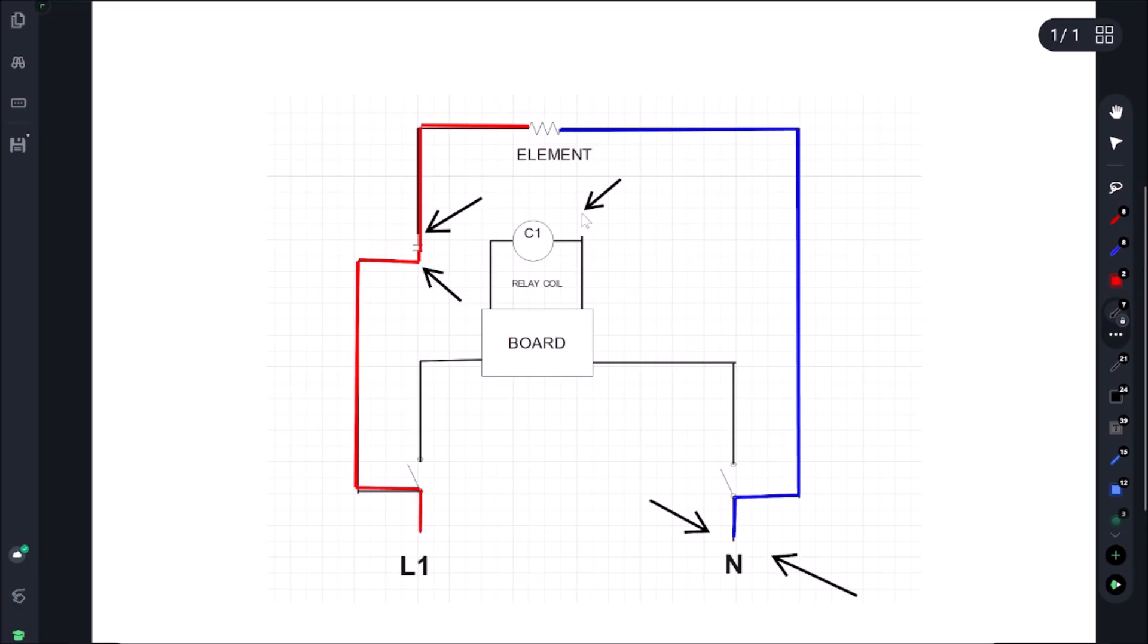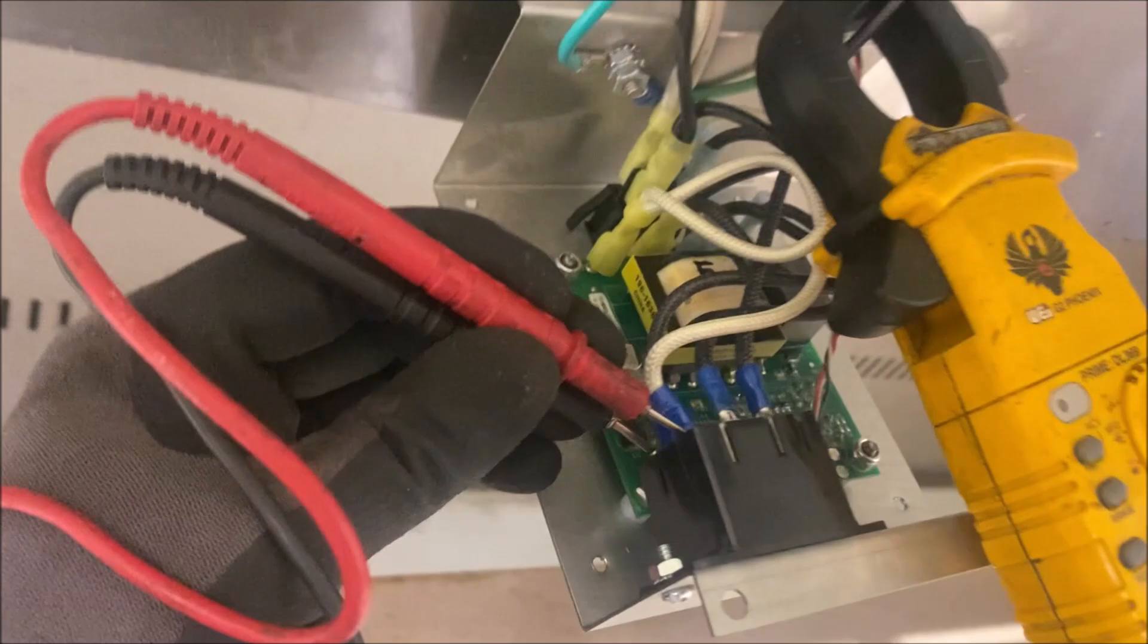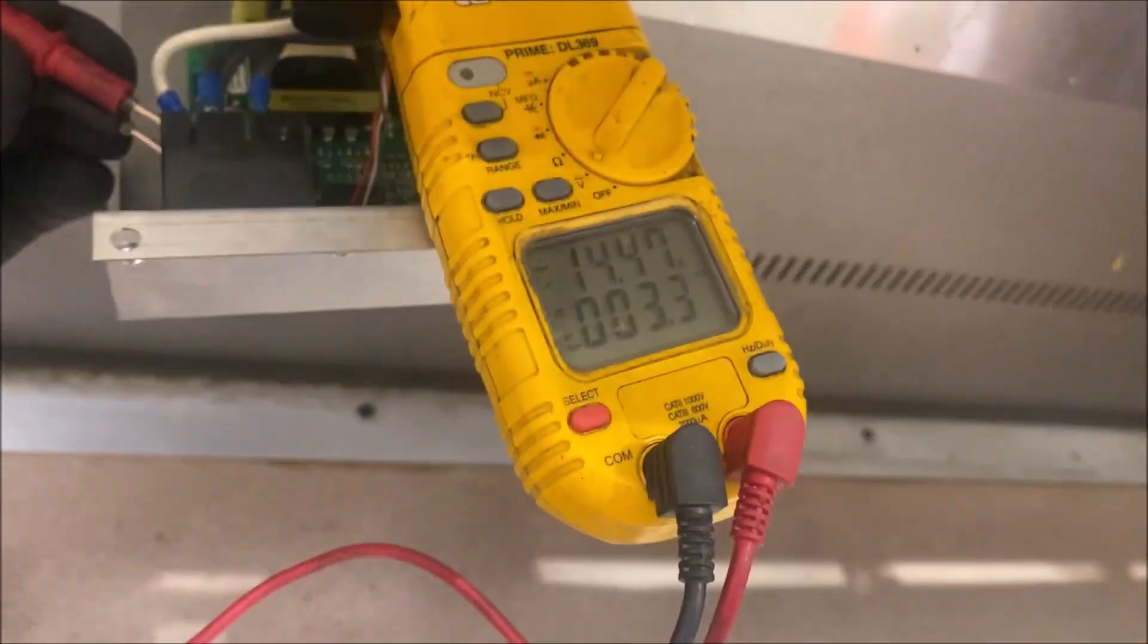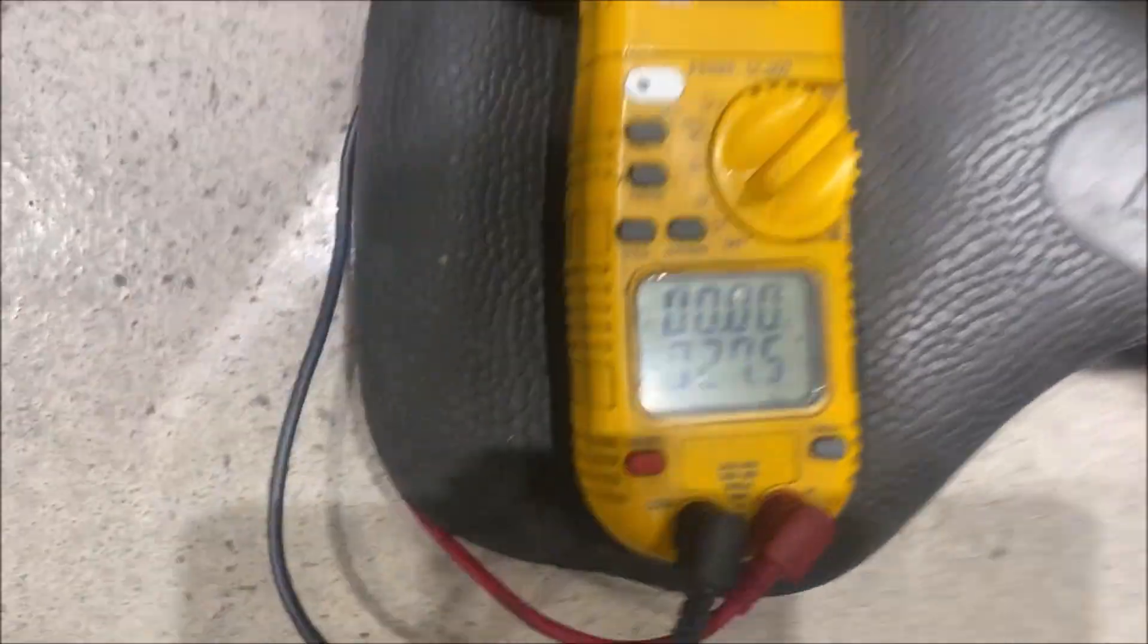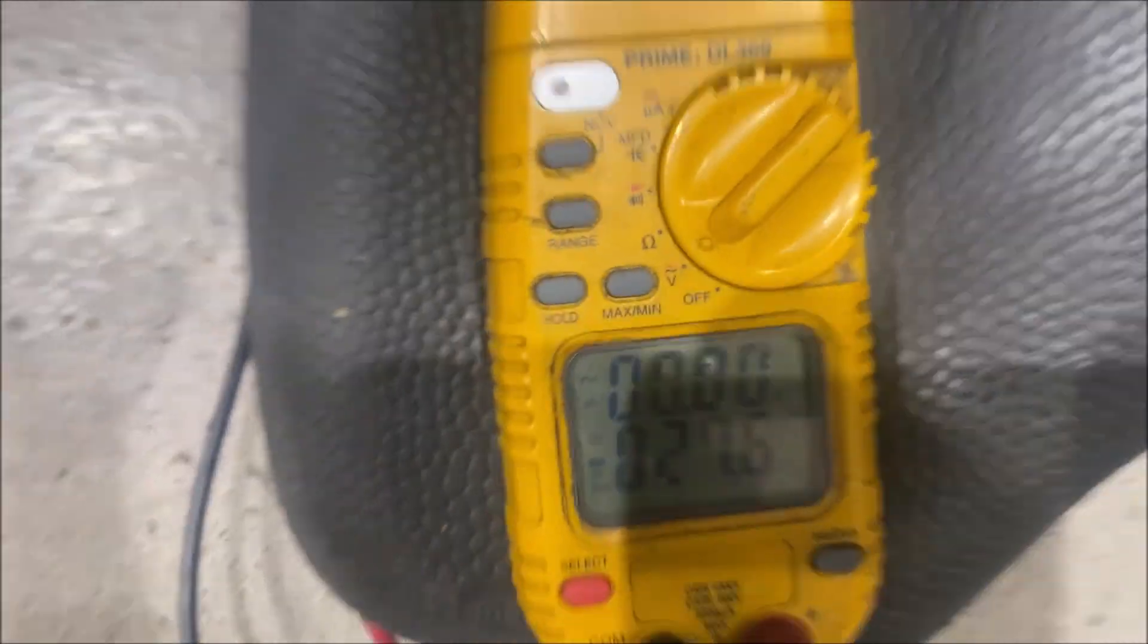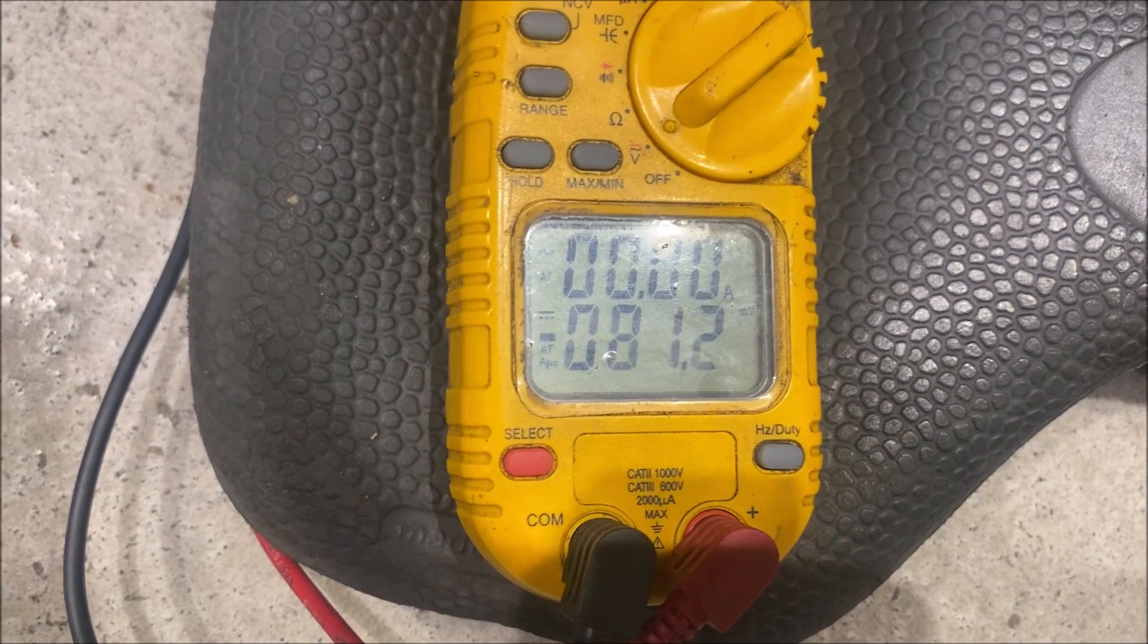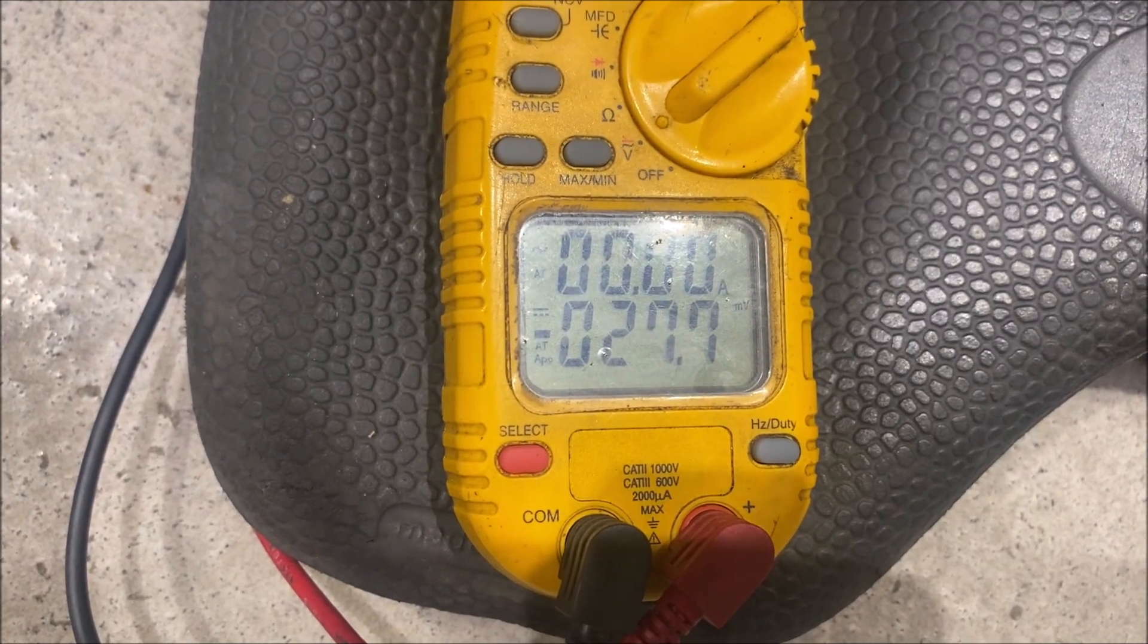The next thing we want to test is let's just make sure there's no power on this coil. If we're getting power to this coil, most likely this board is bad. So let's go test that coil really quickly. We're set to DC voltage. We have zero volts there. So what I'm going to do next now is turn on the unit and you can see we have 27 volts DC. So that's telling me the board is good.